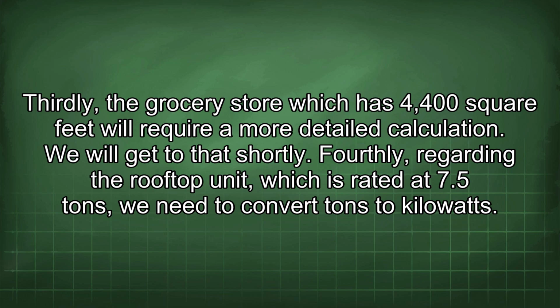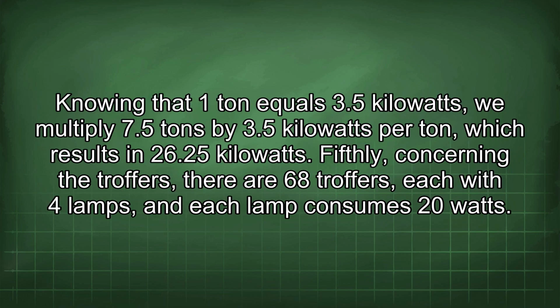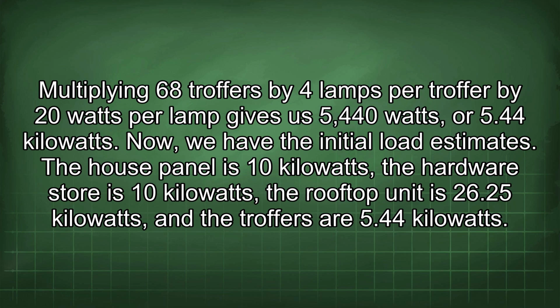Thirdly, the grocery store, which has 4,400 square feet, will require a more detailed calculation. We will get to that shortly. Fourthly, regarding the rooftop unit, which is rated at 7.5 tons, we need to convert tons to kilowatts. Knowing that 1 ton equals 3.5 kilowatts, we multiply 7.5 tons by 3.5 kilowatts per ton, which results in 26.25 kilowatts. Fifthly, concerning the troffers, there are 68 troffers, each with 4 lamps, and each lamp consumes 20 watts. Multiplying 68 troffers by 4 lamps per troffer by 20 watts per lamp gives us 5,440 watts, or 5.44 kilowatts.